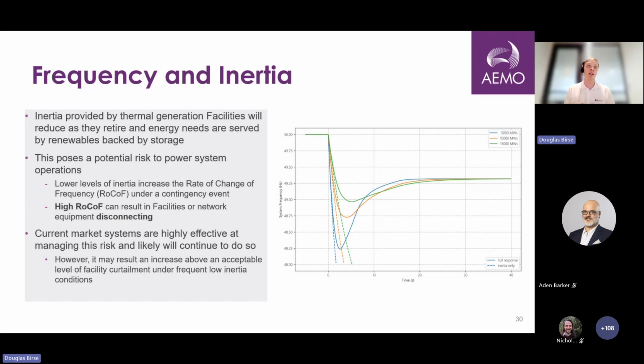Now, when that rate of change of frequency is very high, there's a risk that facilities or network equipment disconnects, and that can result in cascading failure. So multiple loss of generation under a single event. What the example is on that figure here, and I'll hopefully explain this, is that an event occurs, and our frequency normally sits at 50 Hertz. When that event occurs and you lose generation, the frequency drops. Depending on the level of inertia on the system, the three examples here, from blue to orange to green, show increasing levels of inertia on the power system. The rate of change of frequency in those initial fractions of a second decreases. So if you don't have sufficient inertia on the system, that rate of change of frequency is very high, such that you risk losing network equipment or a facility.